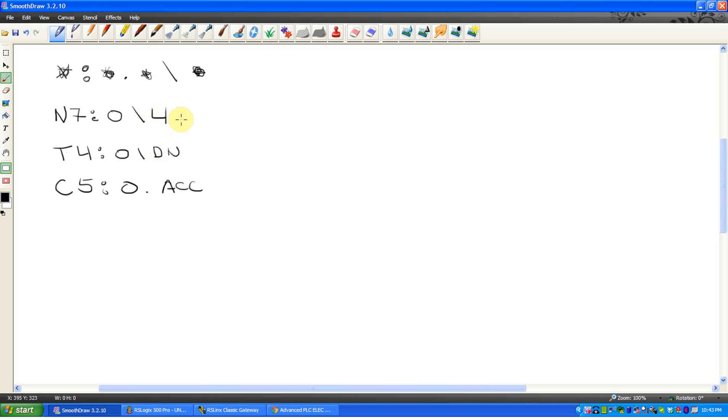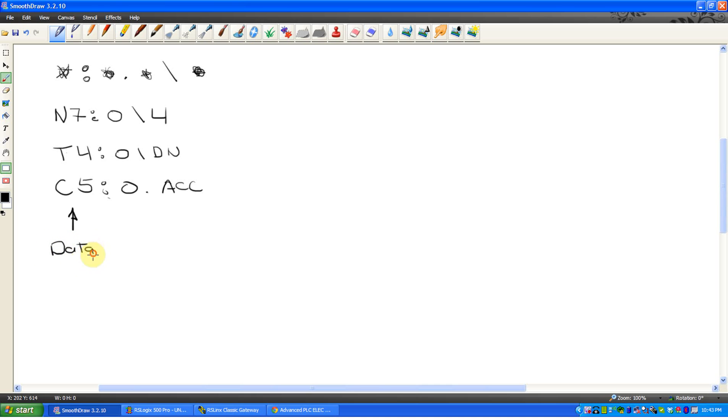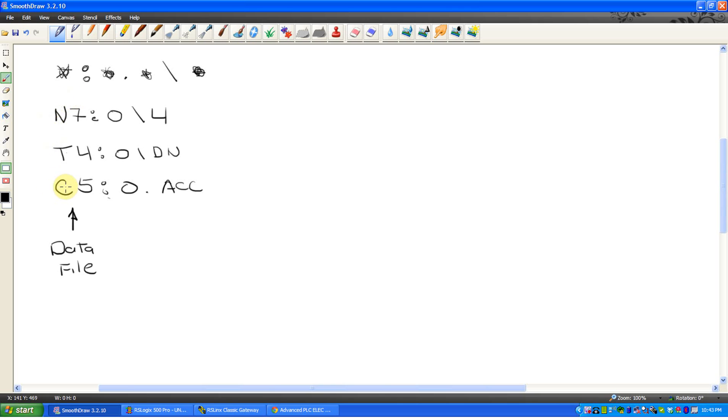And this is where I think people tend to get confused. Anything that's falling here in front of the colon is always referring to the data file. So in that list we looked at, C5 is a data file, T4 is a data file, N7 is a data file. This is the data file. Anything in front of a colon is always a data file. The first digit after can change a bit, unfortunately.